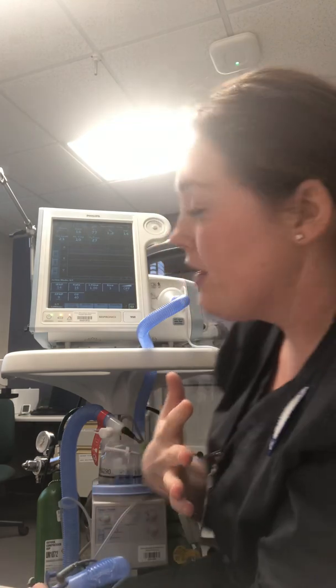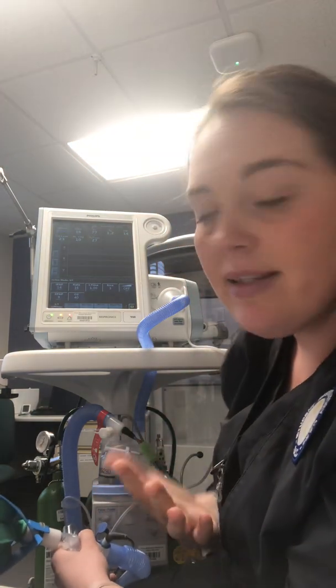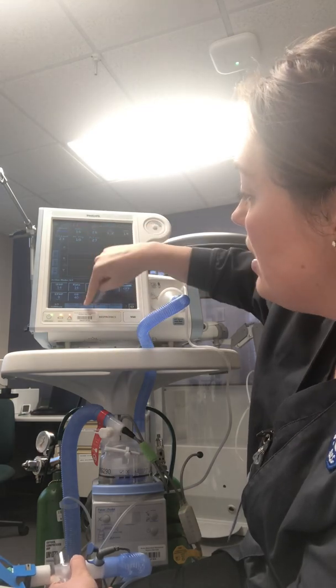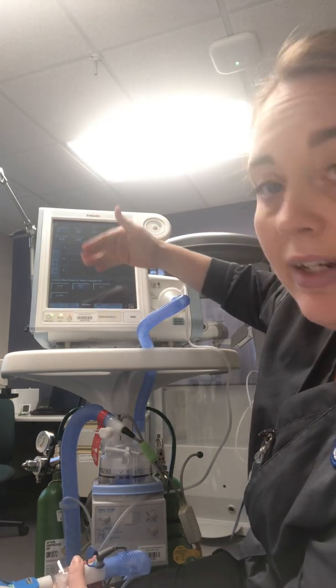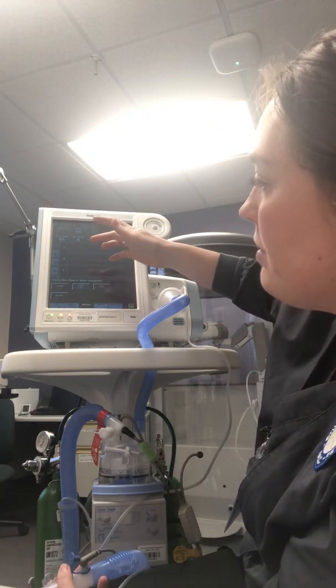This type of system also is not just a Bipap, it's BiPAP, AVAPS, and a CPAP system. So the difference between the BiPAP and the CPAP is that CPAP is giving one constant pressure throughout inhalation and exhalation. With BiPAP, you're getting pressure, but your pressure against exhalation is not as strong as the pressure against inhalation. So the pressure does change between the two cycles of breathing. So that's just sort of the basics. If you want to change it to CPAP or AVAPs, you just click modes and then you have your options. So right now we're on spontaneous timed BiPAP, which is the most common. And then you could of course choose CPAP if you wanted, but that is basically how you run this system.